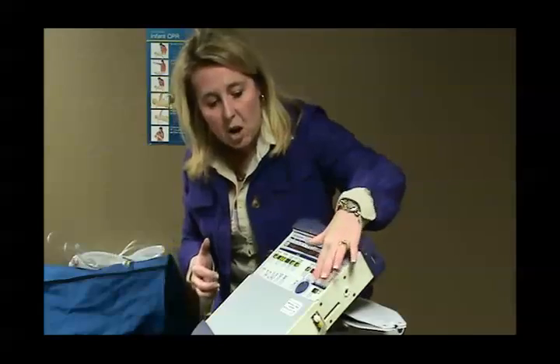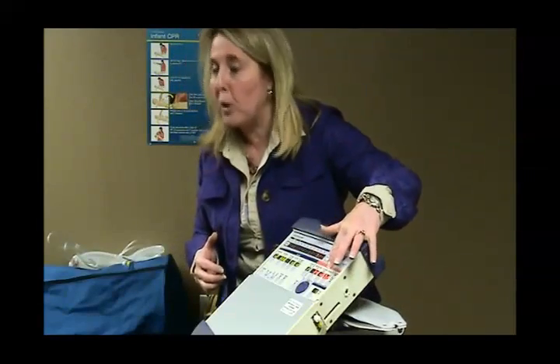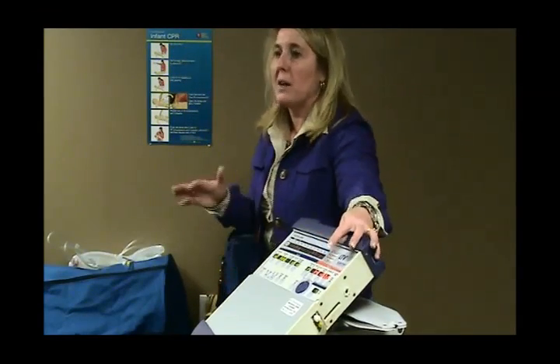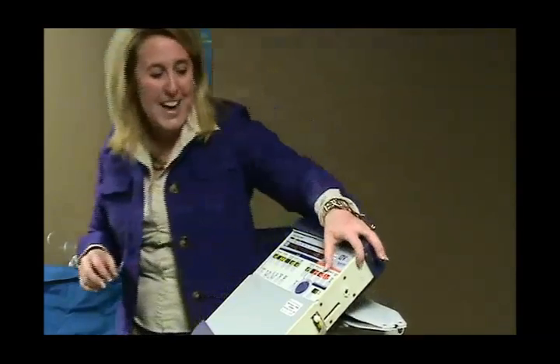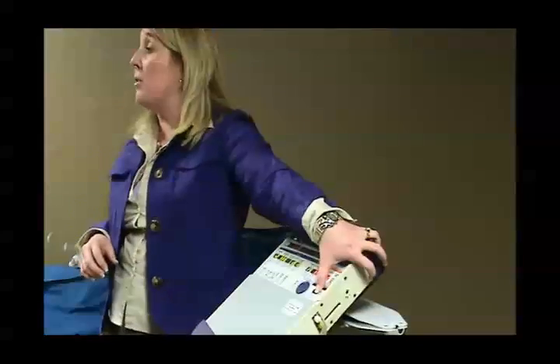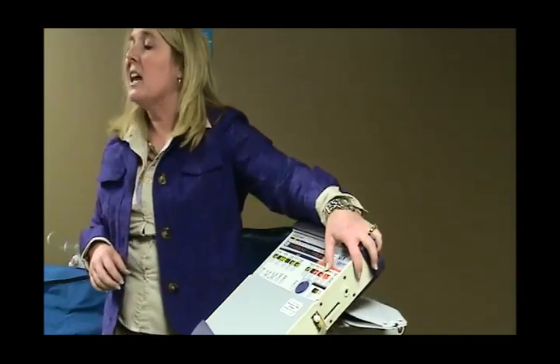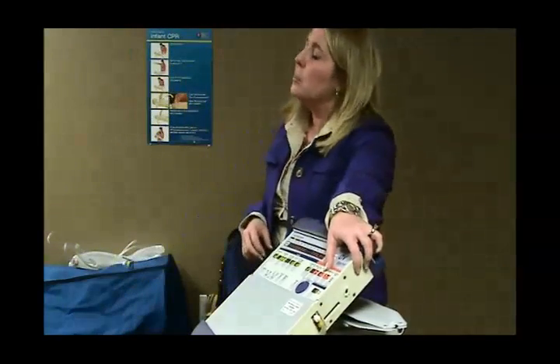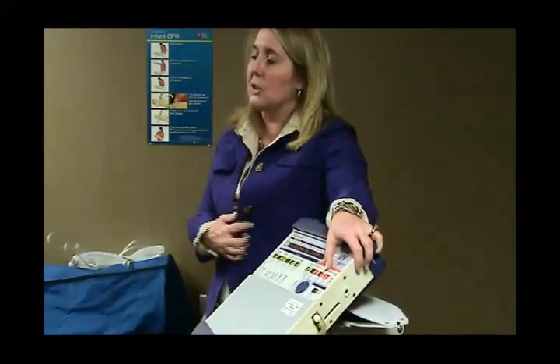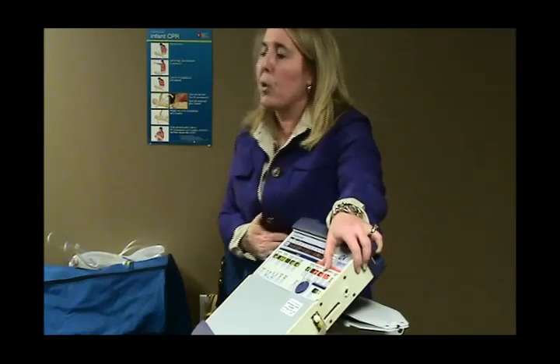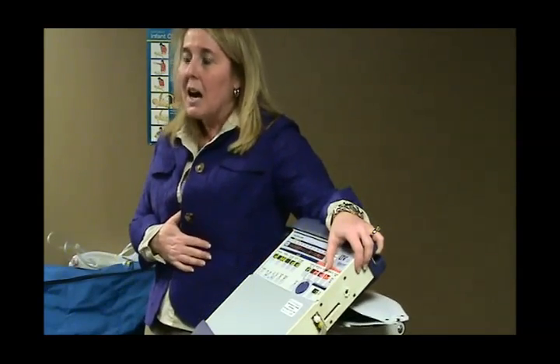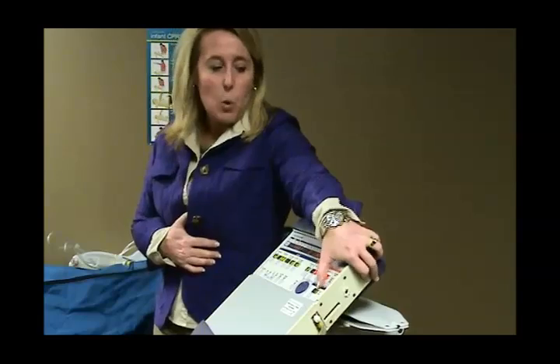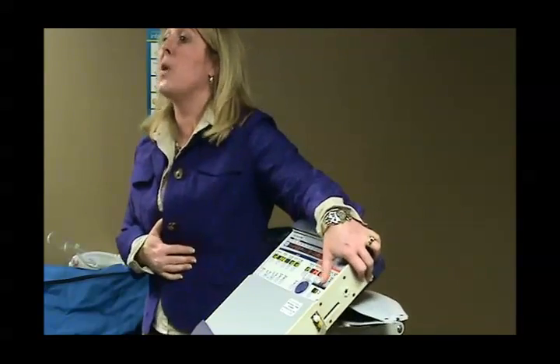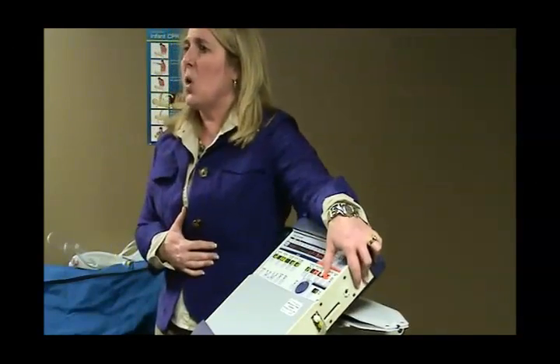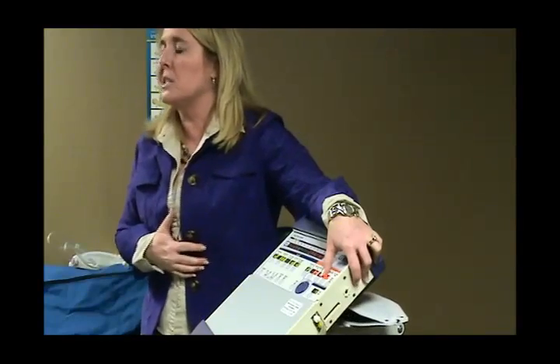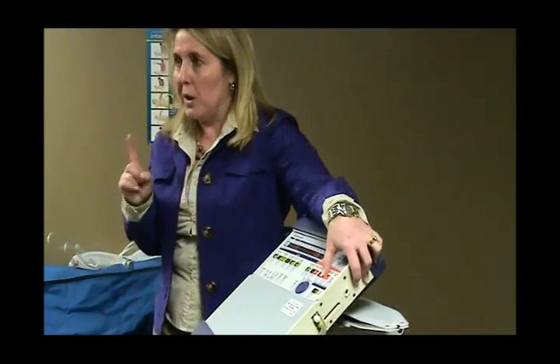The second alarm across here is your low pressure alarm. Again, you guys should never have to change that. That will always be set above PEEP, okay? And if it's set on a specific number, please do not, and teach the nurses, please do not manipulate it. There's probably a reason it is set higher. So I've had people say, well, that only needs to be above PEEP, and my PEEP was 5 and it was set on 10, so I don't want to get any nuisance alarms, so I'm going to put it at 6. Here's the reason you don't want to do that.